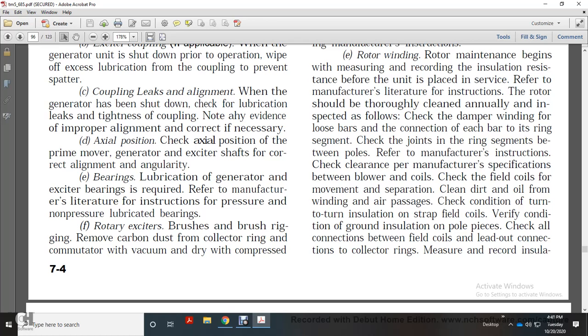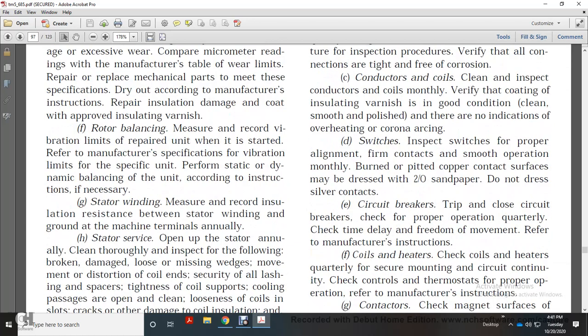Check the field coil for movement and separation. Check for dust and oil in the winding and the air passages. Check the condition of turn-to-turn insulation on strap field coils, and verify the condition of the ground insulation on pole pieces. Check all connections between field coils and lead-out connections to the collector rings, and measure and record insulation resistance.